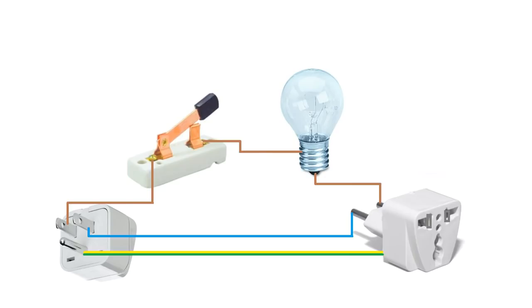Very important guys, keep in mind, keep the right polarization. Why? Because if there is voltage in the chassis of the equipment you are trying to test, you don't want to find out with your hands. So keep the right polarization on it.